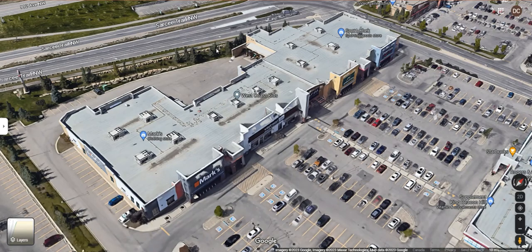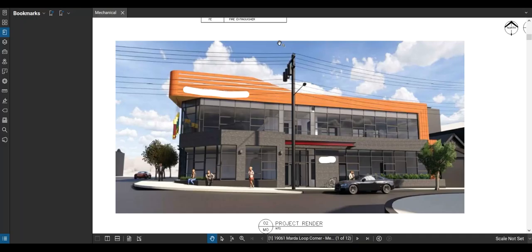Again, not a mechanical engineer, but my understanding is that decentralized systems are very flexible for design purposes when you don't know what your tenants are going to be over the years. The centralized system is a more efficient system but costs more up front. Also, the taller your building gets, the more complicated a decentralized system becomes because you have to get air from the roof down to every space. It would become unfeasible at some point in a tall building.